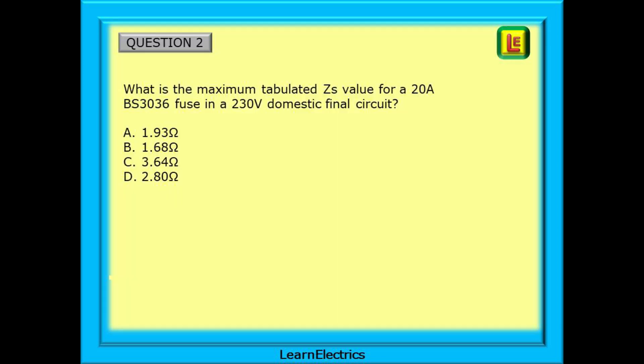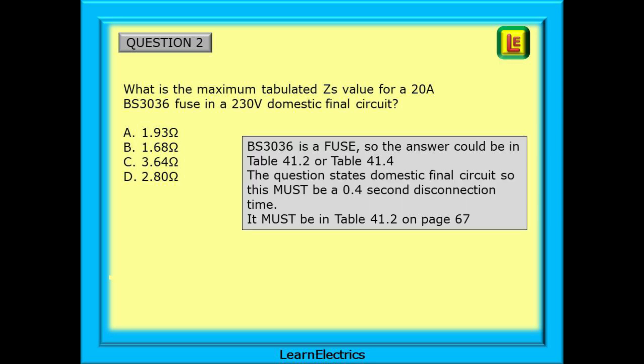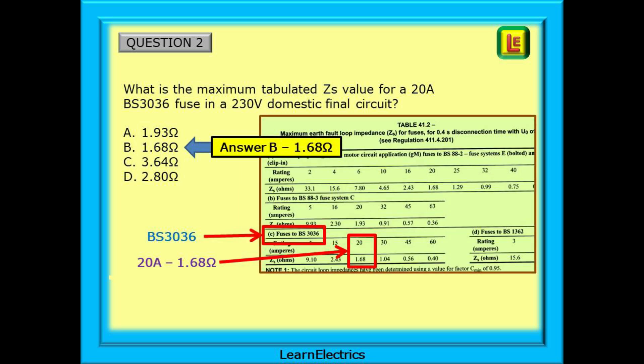Let's have an exam-style question on these tables. What is the maximum tabulated ZS value for a 20 amp BS 3036 fuse in a 230 volt domestic final circuit? BS 3036 is a fuse, so the answer could be in Table 41.2 or Table 41.4. The question states domestic final circuit, so this must be a 0.4 second disconnection time. Therefore the answer must be in Table 41.2 on page 67. Find BS 3036 fuses on page 67, find the entry for 20 amps, and read off the maximum ZS. The answer we choose should be answer B — 1.68 ohms.